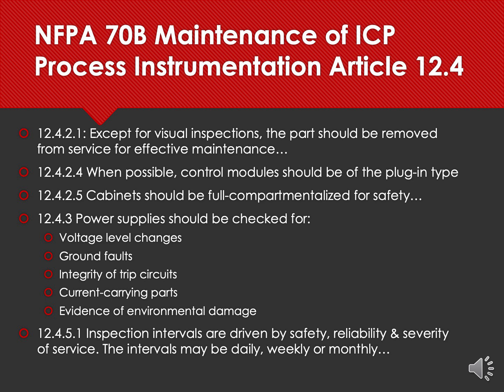For example, if you're in a highly corrosive or a salty environment near a coast, or it could also be from solvents that are used in the vicinity of the equipment. And in terms of the intervals for inspection, well, that's going to be driven by need. If there are safety implications, for example, circuit breakers that have been reset frequently, or reliability considerations, or the severity of service. In other words, if they've been subjected to current flows at or near their limits, the intervals may need to be shortened up or tightened up, and the maintenance may be more aggressive.